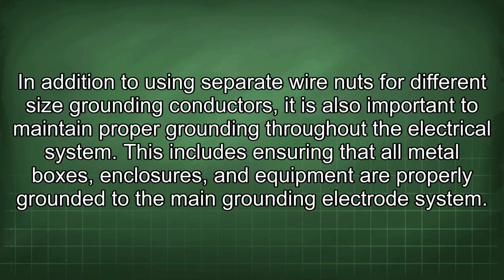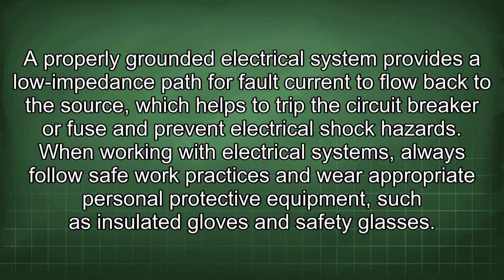In addition to using separate wire nuts for different size grounding conductors, it is also important to maintain proper grounding throughout the electrical system. This includes ensuring that all metal boxes, enclosures, and equipment are properly grounded to the main grounding electrode system. A properly grounded electrical system provides a low impedance path for fault current to flow back to the source, which helps to trip the circuit breaker or fuse and prevent electrical shock hazards.